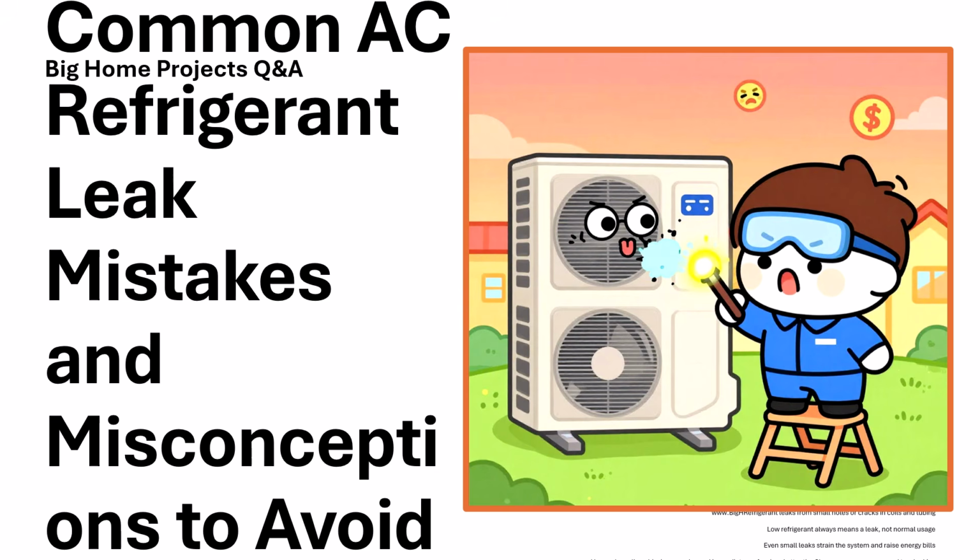One thing most people do not know is that a lot of these leaks are actually caused by something called formicary corrosion, which happens when tiny amounts of acid from household cleaners, paint fumes, or even candles react with the copper coils and create pinhole-sized leaks that are almost invisible to the eye. This process can take months or even years before you notice your home is not cooling properly.